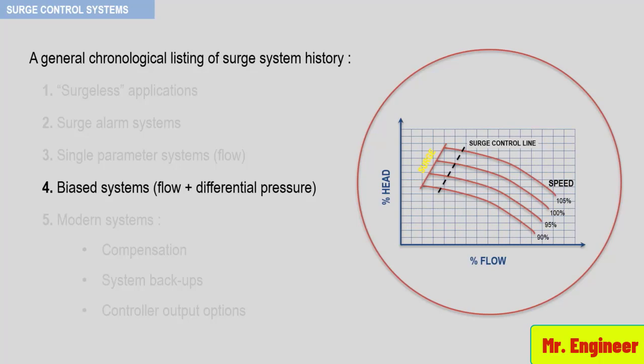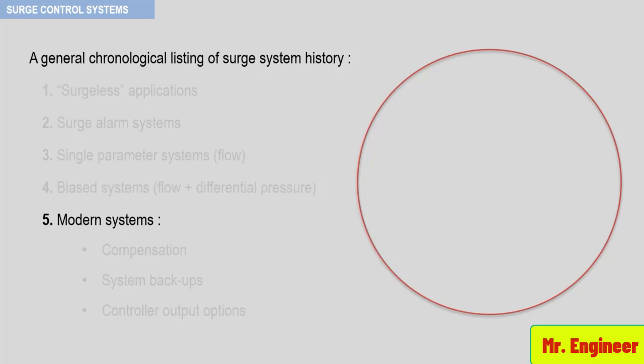The final system in the evolution of surge controls is the modern microprocessor system, which affords many options to protect the compressor against surge. These systems usually employ compressor inlet and discharge temperature inputs, in addition to flow and differential pressure for each compressor section. Examine the relationship for polytropic head as seen previously, and you will see that this approach yields a more accurate approximation of the operating point. This is because input of temperature at the inlet and discharge of the compressor allows the calculation of the following terms highlighted in blue.